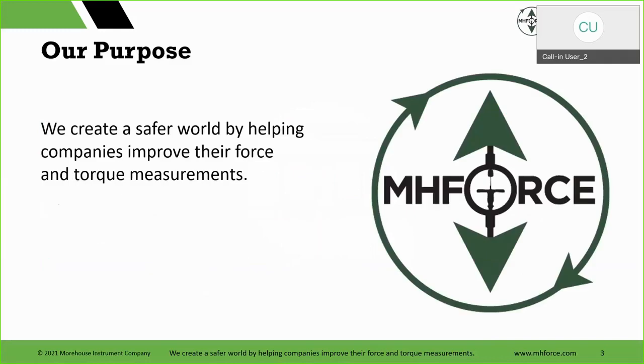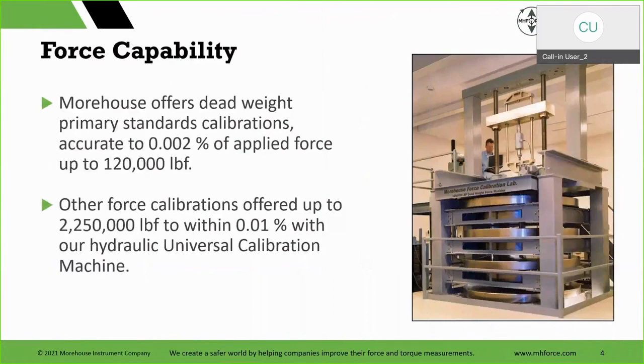So our purpose at Morehouse is to create a safer world by helping companies improve their force and torque measurements. A little bit more background about us. We do have a calibration laboratory where we offer force and torque calibrations at a very high level of accuracy. We are a primary standards laboratory and offer deadweight calibrations for up to 120,000 pounds of force, known to within 0.002% of applied force. We also offer other force calibrations up to 2.25 million pounds or 10 meganewtons of force, known to within 0.01% of applied force.